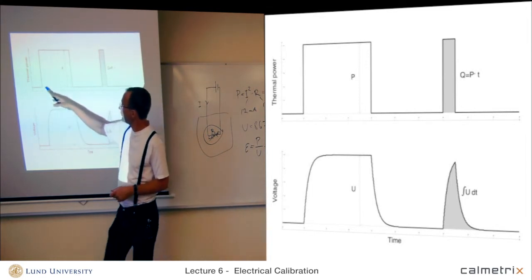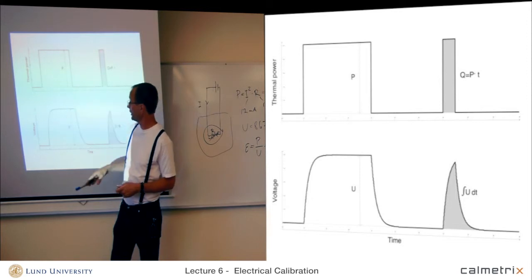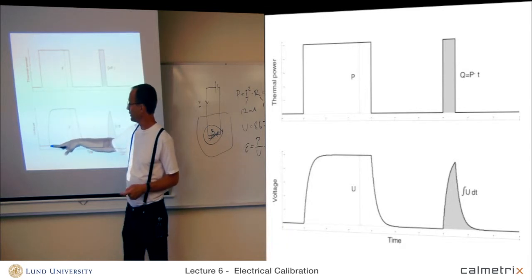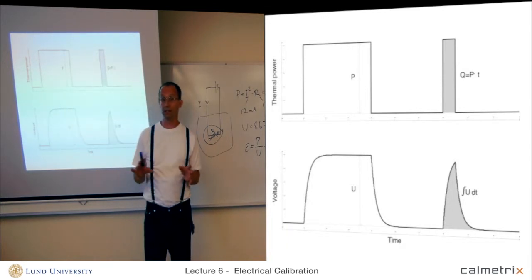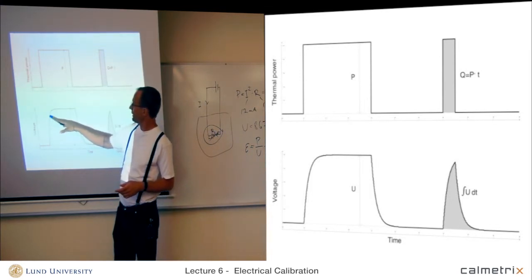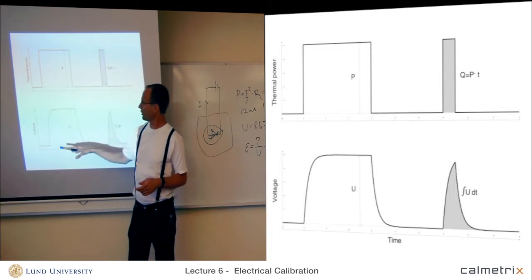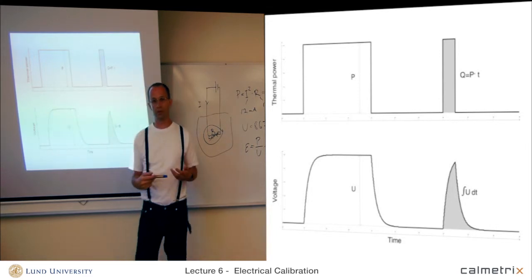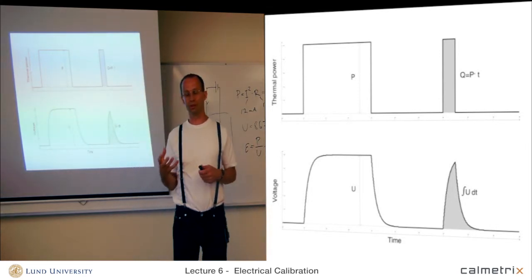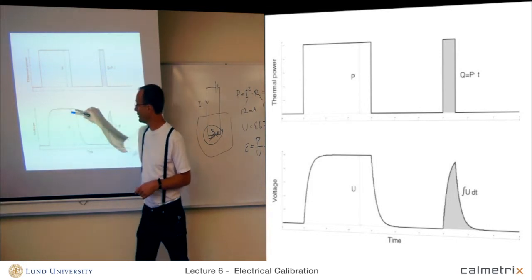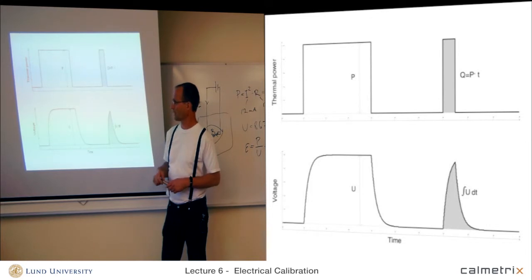As you see, the thermal power input is like a rectangular pulse or a square pulse. But the voltage output from the calorimeter, it doesn't have the same shape. And as we come back in a later lecture, how we can correct for that. The reason it goes up asymptotically like this is like an exponential function, and there's also an exponential function going down here, is that there is a thermal inertia of the sample, of the interior of the calorimeter. So, it takes some time to heat the calorimeter up to a certain level, and it takes some time for the heat to flow out or to leak out of the calorimeter.